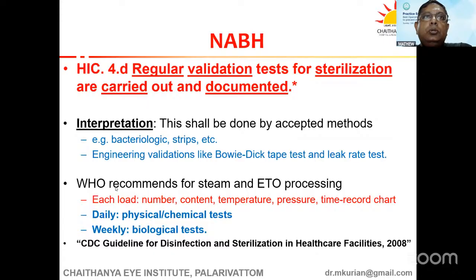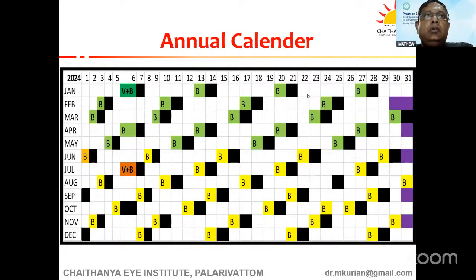The WHO recommendation for this is that each load should have the temperature, pressure, and time record chart. The daily monitoring should be for the physical and chemical tests, and the weekly monitoring should be done by the biological tests. So it's desirable to start off with an annual calendar like this for at least the weekly monitoring. Validation is done every six months. That is the V. And the biological monitoring is done every week. Preferably, we do it on a Saturday so that we have the report on Monday, and no surgery happens after the test is carried out before the report reaches us, and that makes it safe for us.